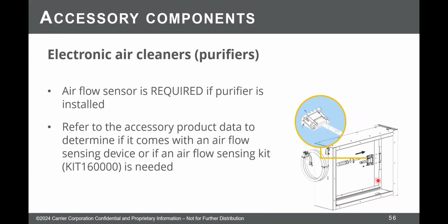If you have an electronic air cleaner or electronic air purifier, in other words, a filter with wires to it, if your filter has wires connected to it, you're required to have an airflow switch. This is the kit number for Bryant Evolution, Carrier Infinity, or the ICP air purifier. That's the kit number that you'd have to provide them with the filter itself, the filter rack itself. So this airflow switch just proves that there is, in fact, air moving through the filter before power is allowed to be applied to the filter.